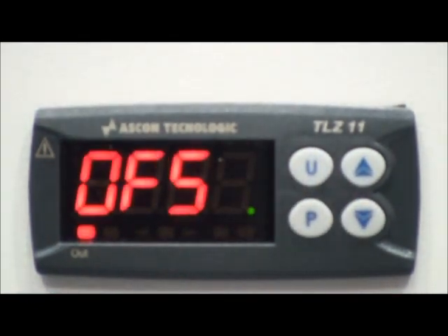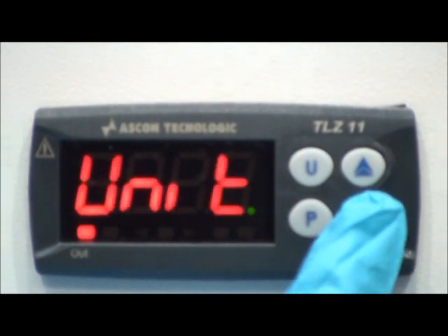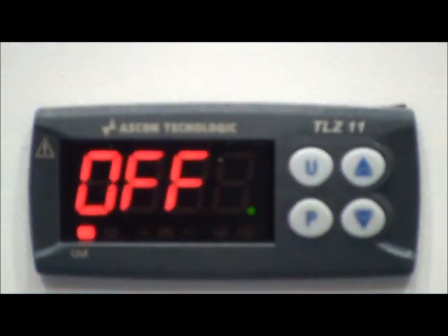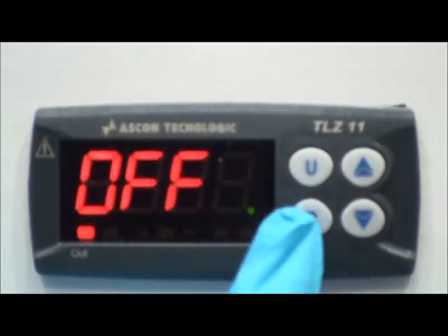At the moment it's set at 12, and we found that 12 is quite unique for our cabinets. So we move on. The next operation is DP. So we press the key, units, DP. DP is off. We move on. Go up. Units, press P, and at the moment we're displaying degrees centigrade. So we press P to accept that's okay. Go down.